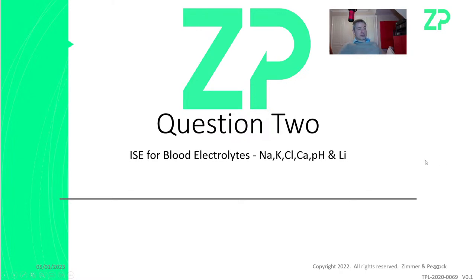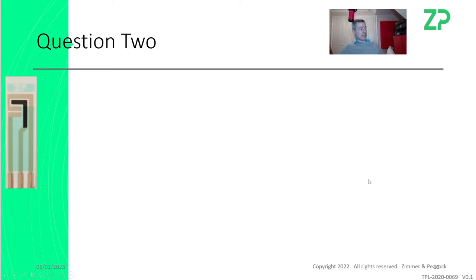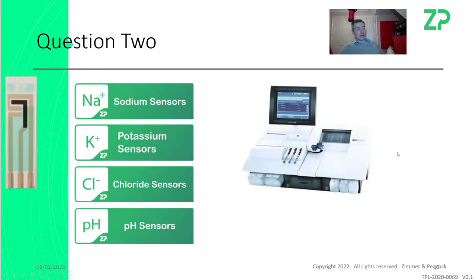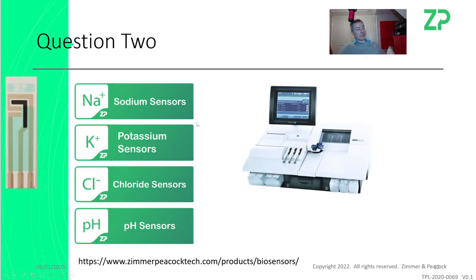Question two: ion-selective electrodes for blood electrolytes. We do have sodium, potassium, chloride, calcium, and pH solid-state ion-selective electrodes. I'll put all links underneath the video. These kind of electrodes are used in real products — Radiometer uses them, though they manufacture their own. They're a multi-billion dollar business.